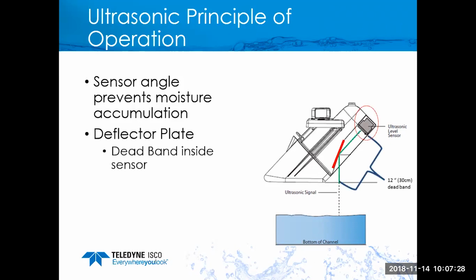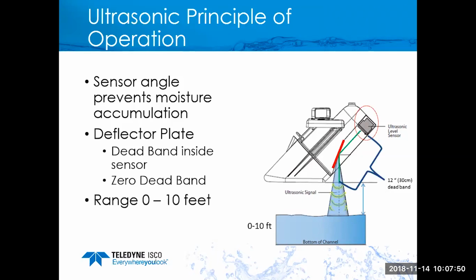The other key thing that we took into account was the dead band. Every ultrasonic pretty much has a dead band. Normally they're 12 inches. This one is similar, a 12-inch dead band. With the design, we've accounted for that 12 inches in the housing. So now we have virtually a zero dead band sensor. The water can go all the way up, including submergence, before it will quit reading level. The ultrasonic has a 10-foot range, so it can be in a dry pipe 10 feet above the minimum flow.